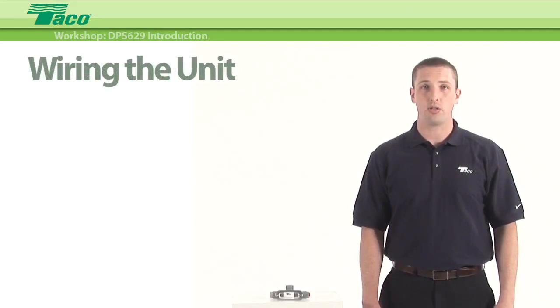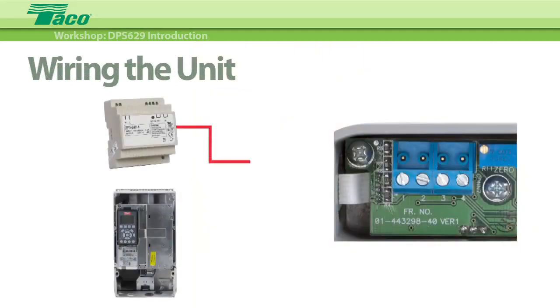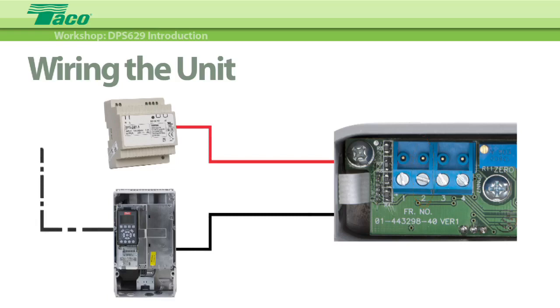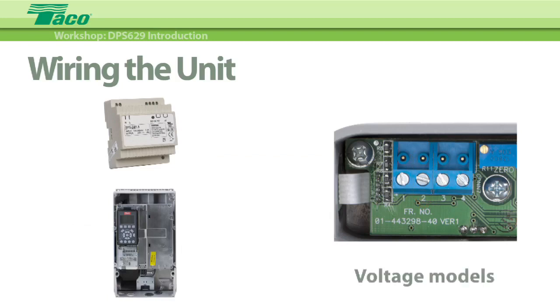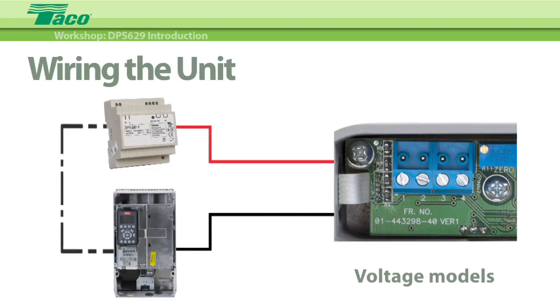Now you're ready to wire the unit. Connect the positive output of the power supply to terminal 1 on the transmitter. For 4 to 20 milliamp output models of the DPS629, connect terminal 2 of the transmitter to the appropriate terminal of the VFD. To complete the circuit, connect the appropriate terminal of the VFD back to the negative output of the power supply. For voltage output models of the DPS629, connect terminal 2 of the transmitter directly to the negative output of the power supply. Connect terminal 3 of the transmitter to the appropriate terminal of the VFD. Then jumper the appropriate terminal of the VFD to the negative output of the power supply.